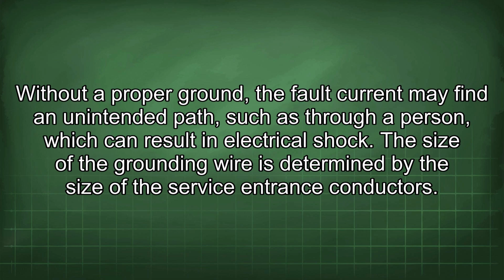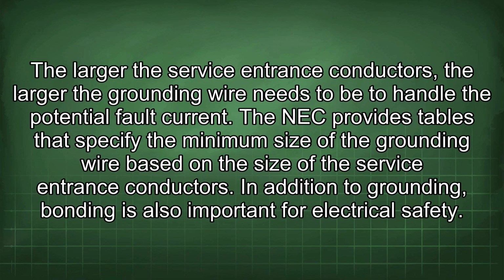The size of the grounding wire is determined by the size of the service entrance conductors. The larger the service entrance conductors, the larger the grounding wire needs to be to handle the potential fault current. The NEC provides tables that specify the minimum size of the grounding wire based on the size of the service entrance conductors. In addition to grounding, bonding is also important for electrical safety.